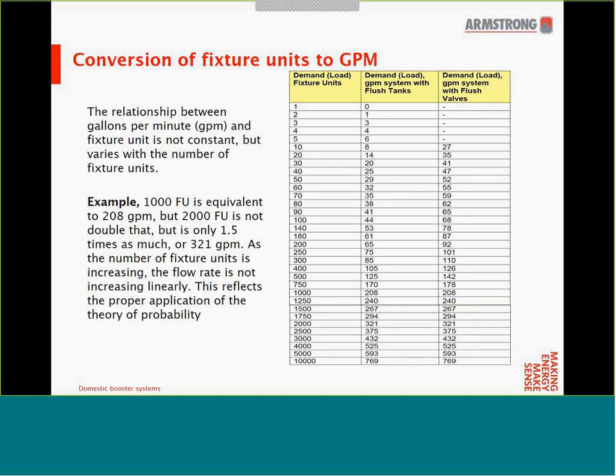For example, if the maximum probable demand for two branches is required, and one branch has a load of 1,000 fixture units and the other has 2,000 fixture units, it would be improper to add 208 GPM plus 321 GPM to obtain 529 GPM. The correct procedure is to add 1,000 and 2,000 fixture units to obtain a total of 3,000 fixture units, and then from the table determine the correct peak load demand as 432 GPM. This value reflects the proper application of the theory of probability.